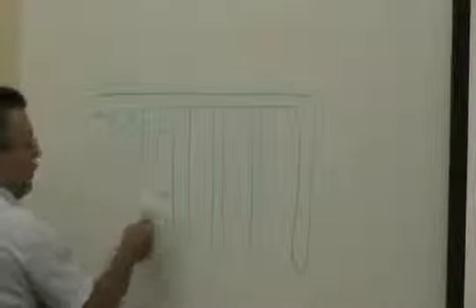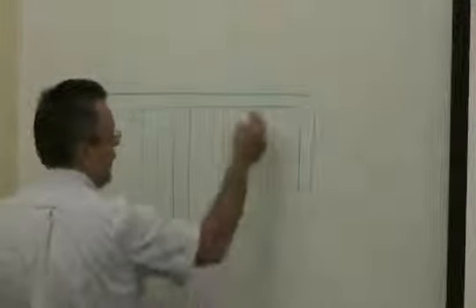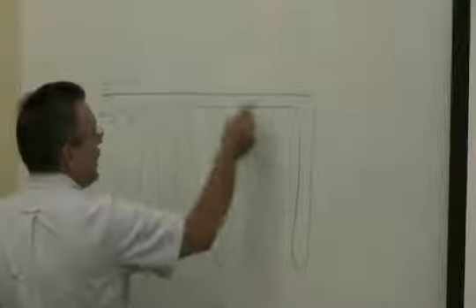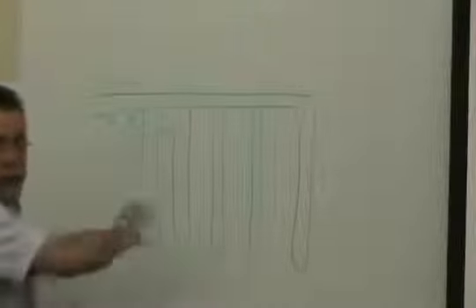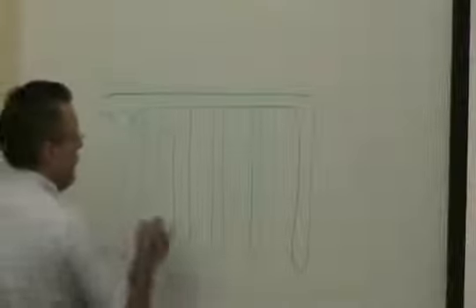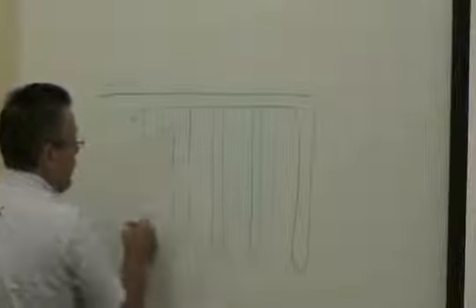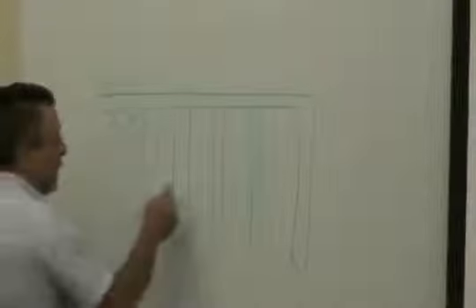That would be 2 series loops. Again, it depends on what your pipe size is, and most of these loops are 3/4 of an inch. Vertical piping. Horizontal is whatever it takes to get all your loops together. Some of these series loops, you've got to be careful about how many you put in series, again, because most of this is 3/4 to 1 inch piping.